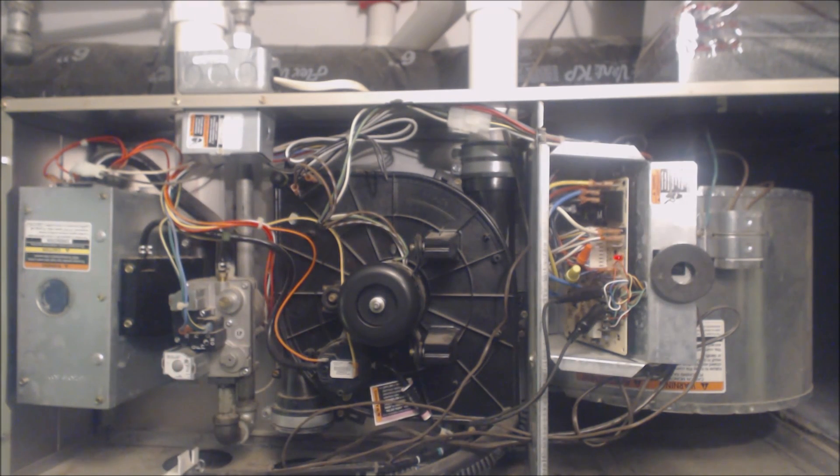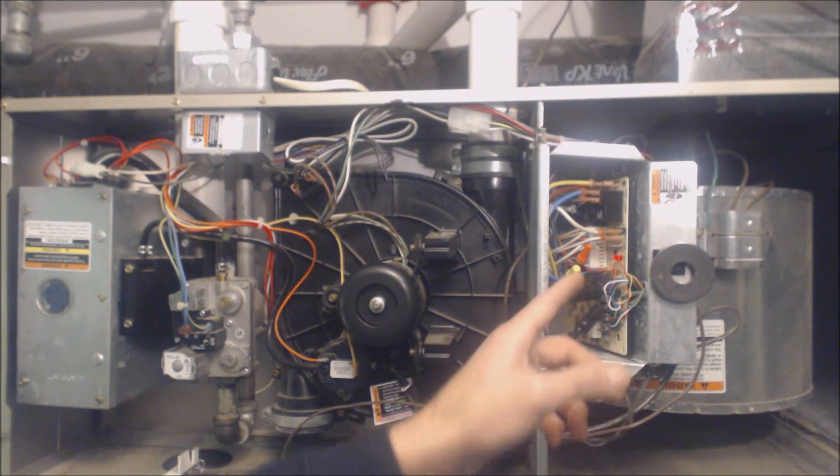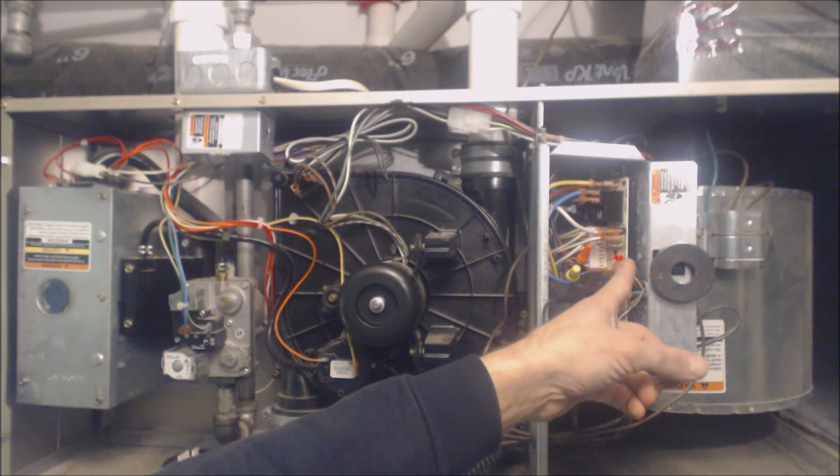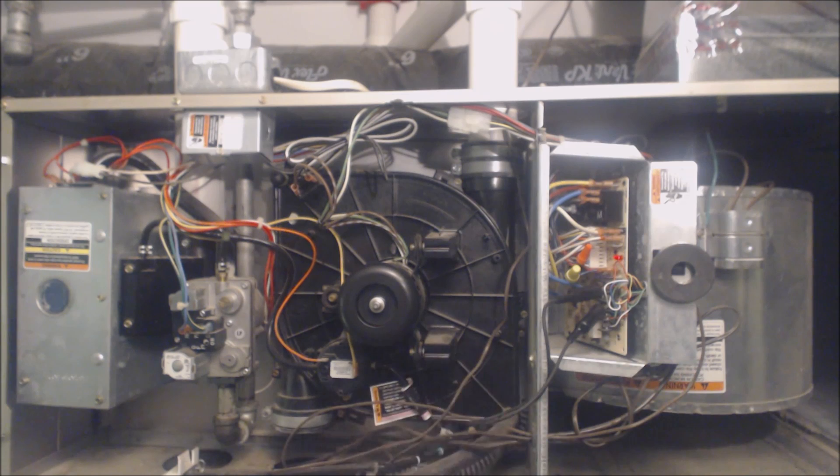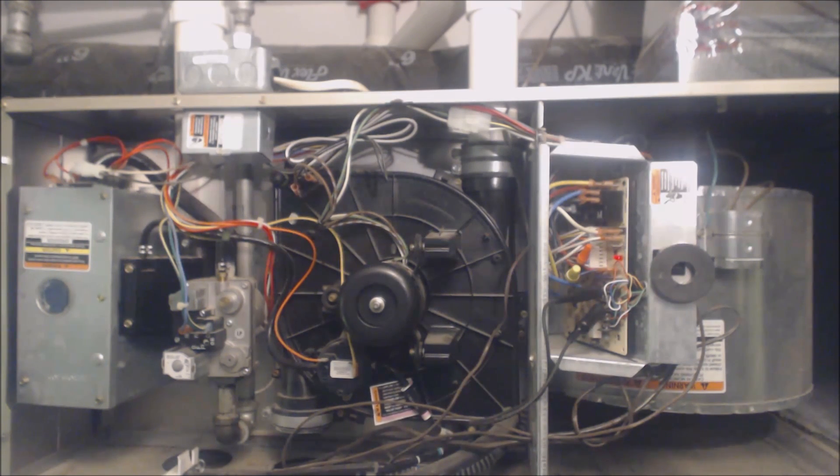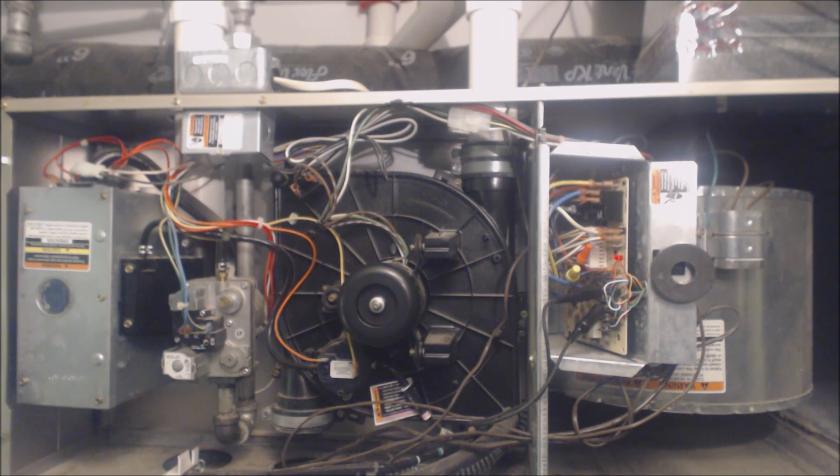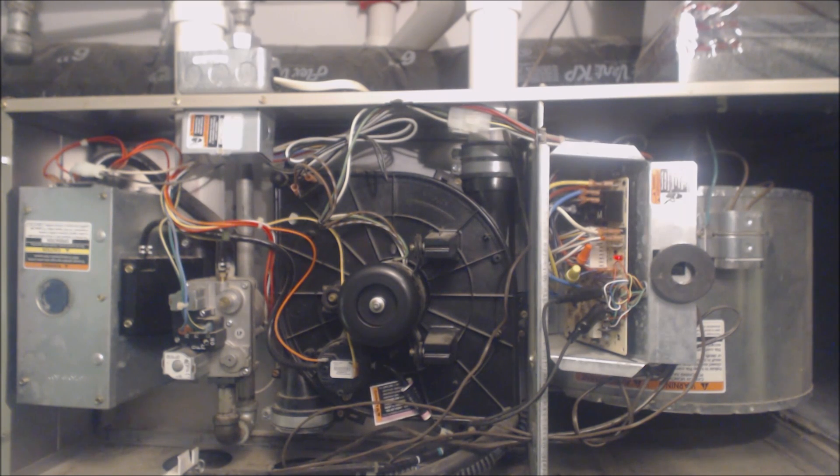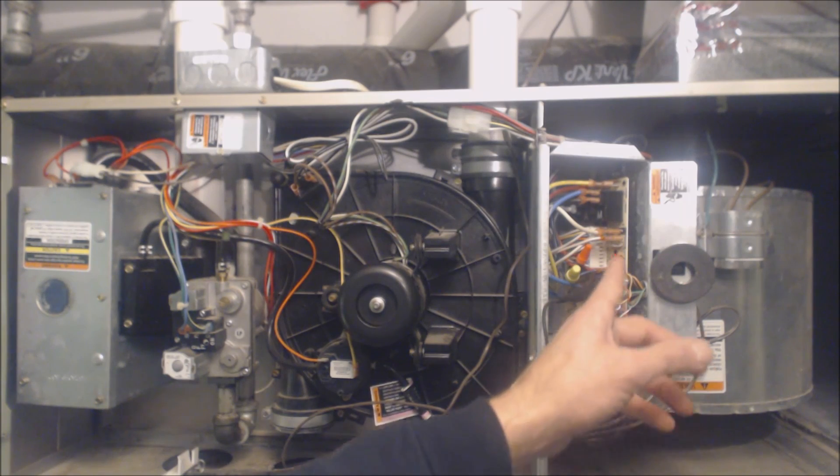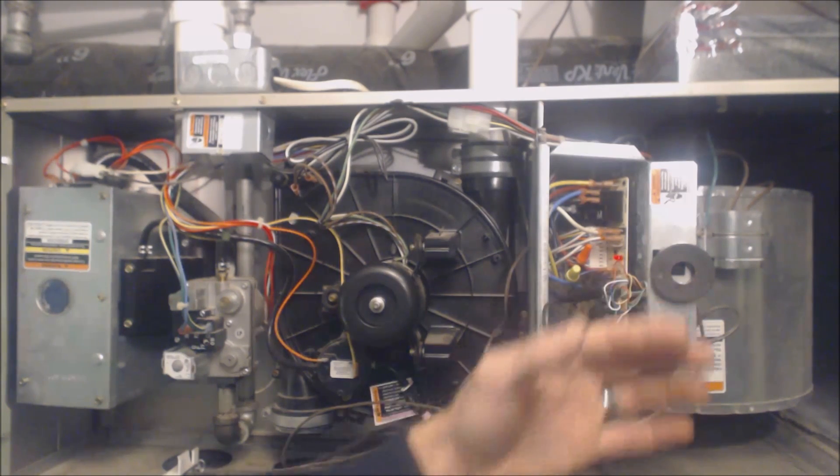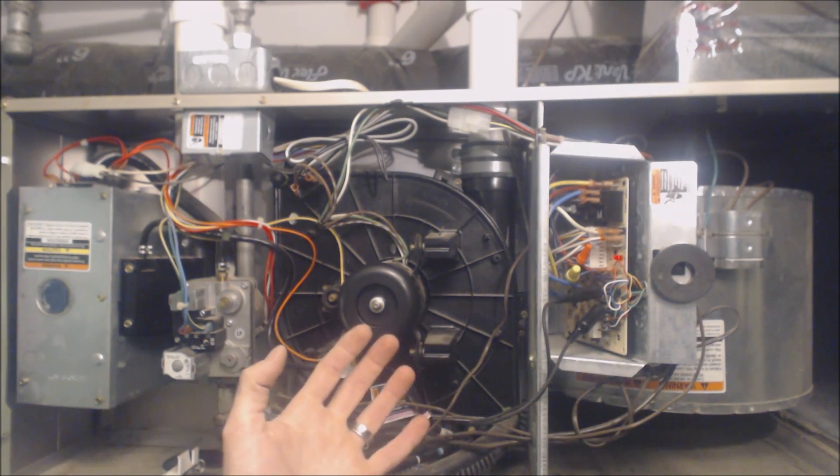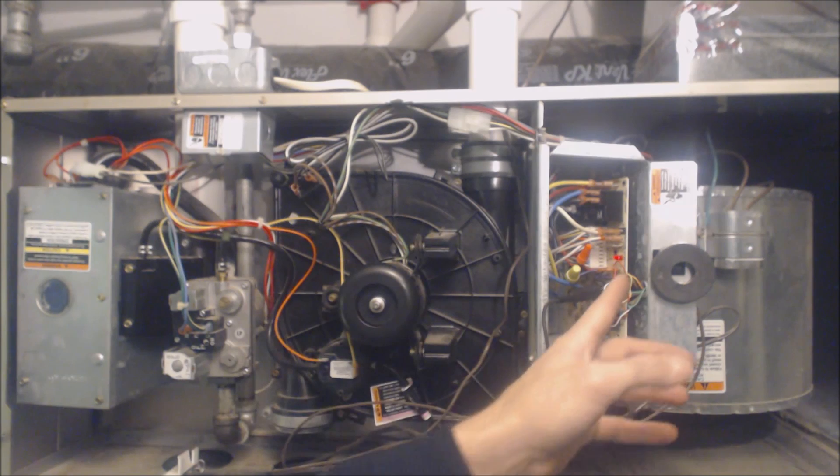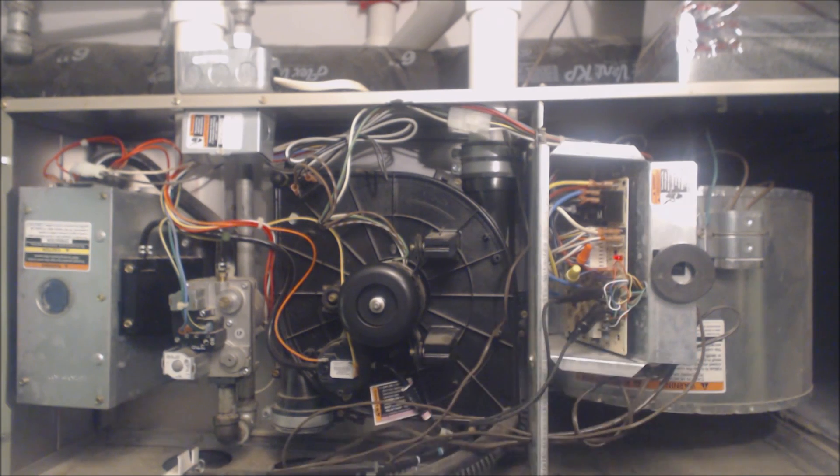Beyond that, you want to always, before you even take the cover off, check out the status code light. If it's flashing, count out the short flashes, count out the long flashes, and then look on the furnace door and see what that means. If there's some type of a fault, like a limit circuit fault, or if it says status code 24, in this case, if it was two short flashes and four long flashes, that would mean that that fuse is blown.